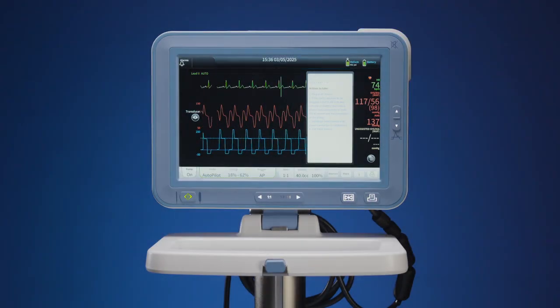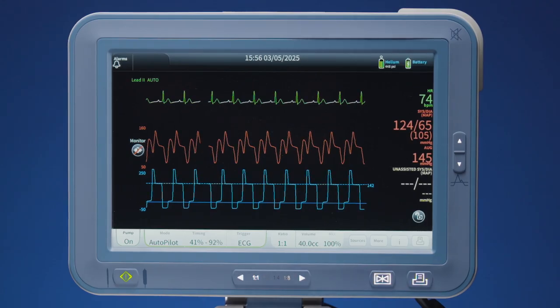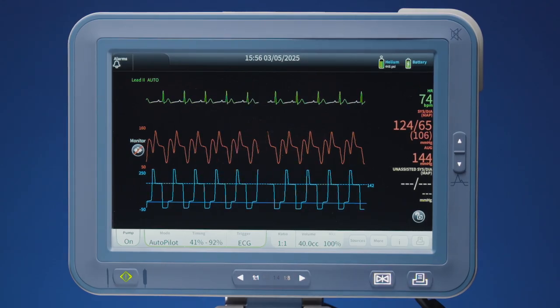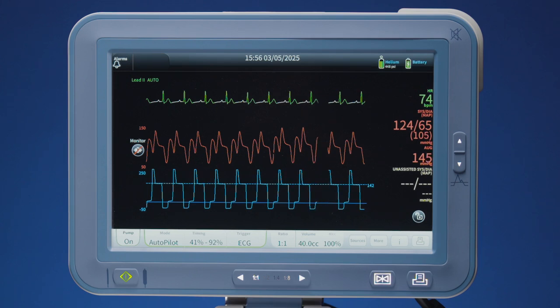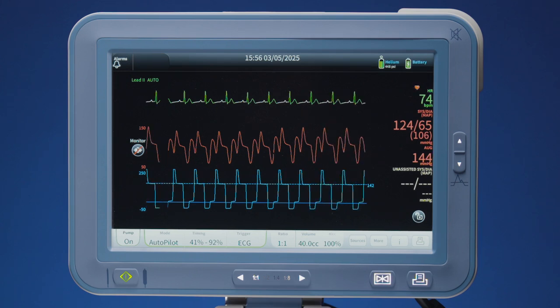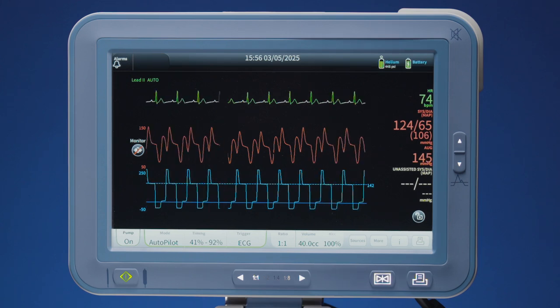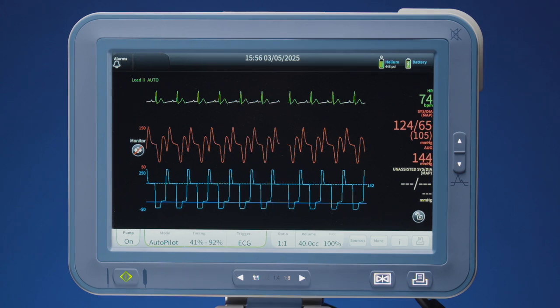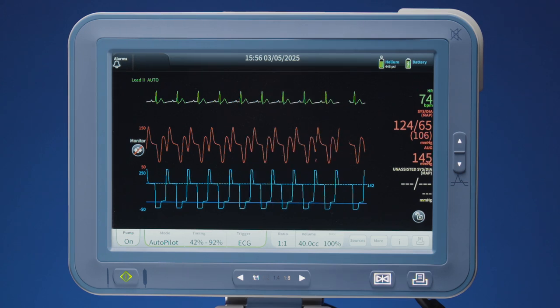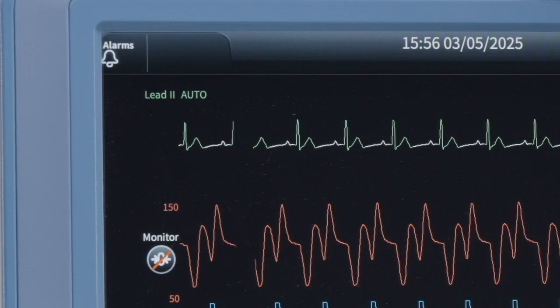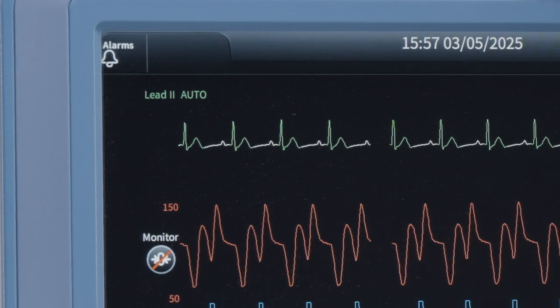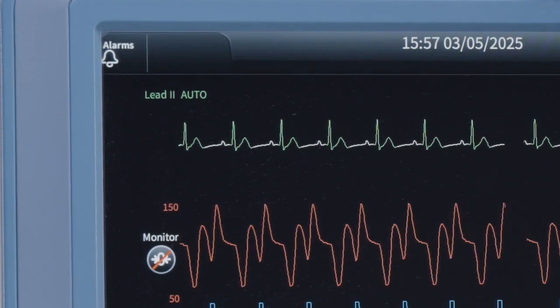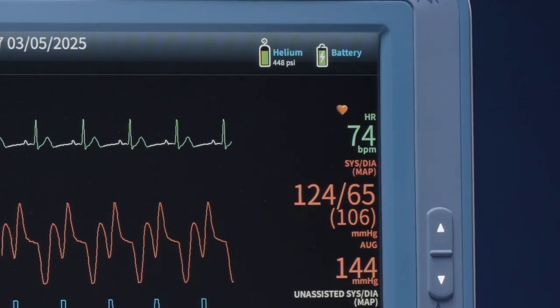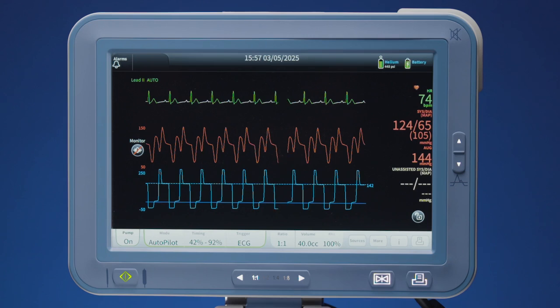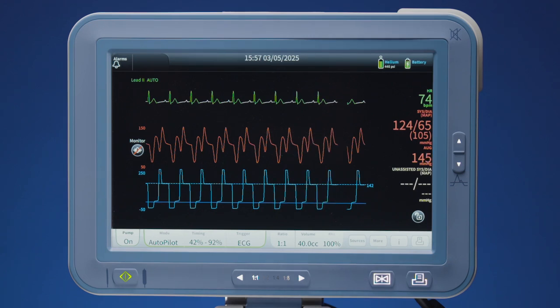The AC3 Optimus IABP display shows 3 waveforms and related data, each in a different color, for easy identification and interpretation. All numeric data is calculated and displayed on a beat-to-beat basis. Heart rate is averaged over 2 seconds. The ECG trace is superimposed with white during assist intervals or expected period of IAB inflation. The heart rate is displayed in green. The ECG source and gain is above the ECG waveform on the left side of the display.